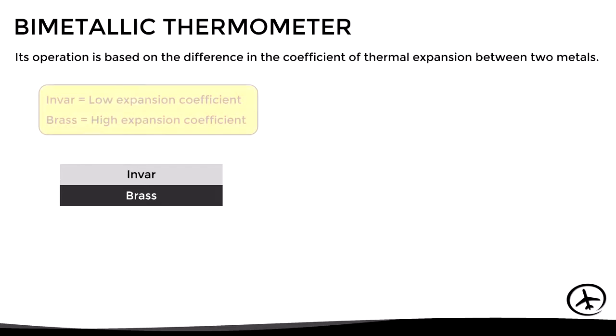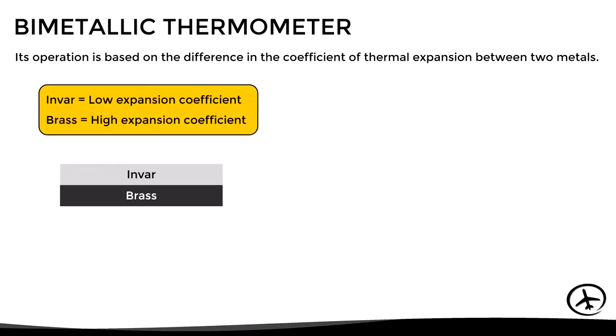Let's start with the bimetallic thermometer. The operation of this type of thermometer is based on the difference in the coefficient of thermal expansion between two metals. Here we have two metal strips: one is made of invar and the other one is made of brass. These metals have different coefficients of thermal expansion — invar has a low coefficient of expansion while brass has a high coefficient of expansion.